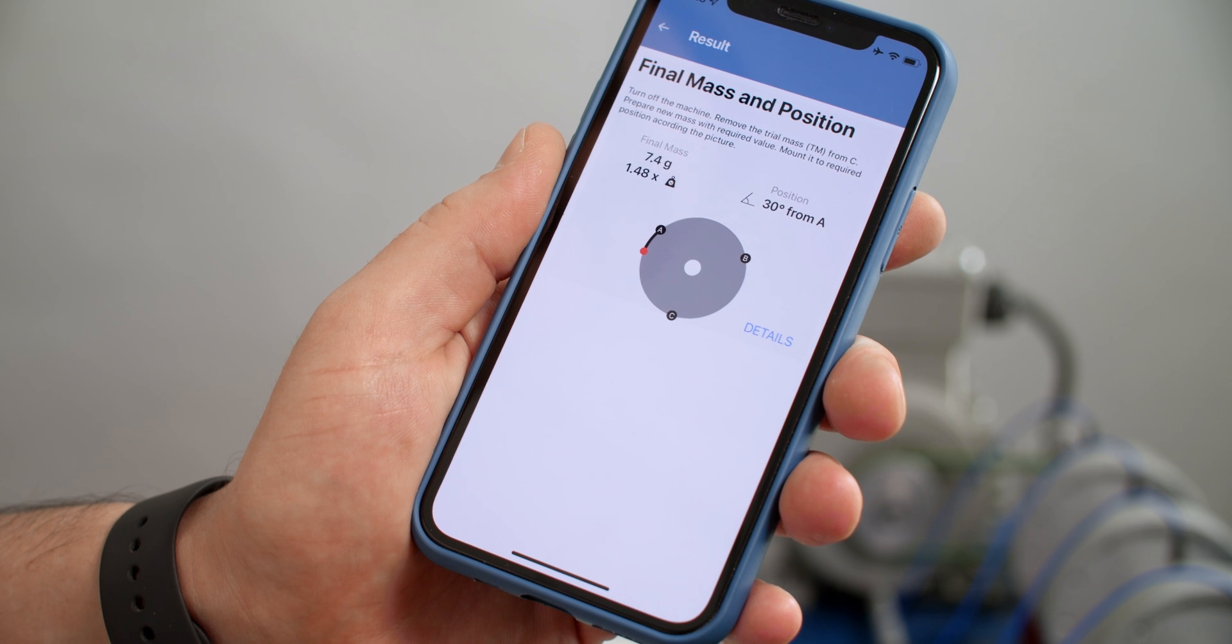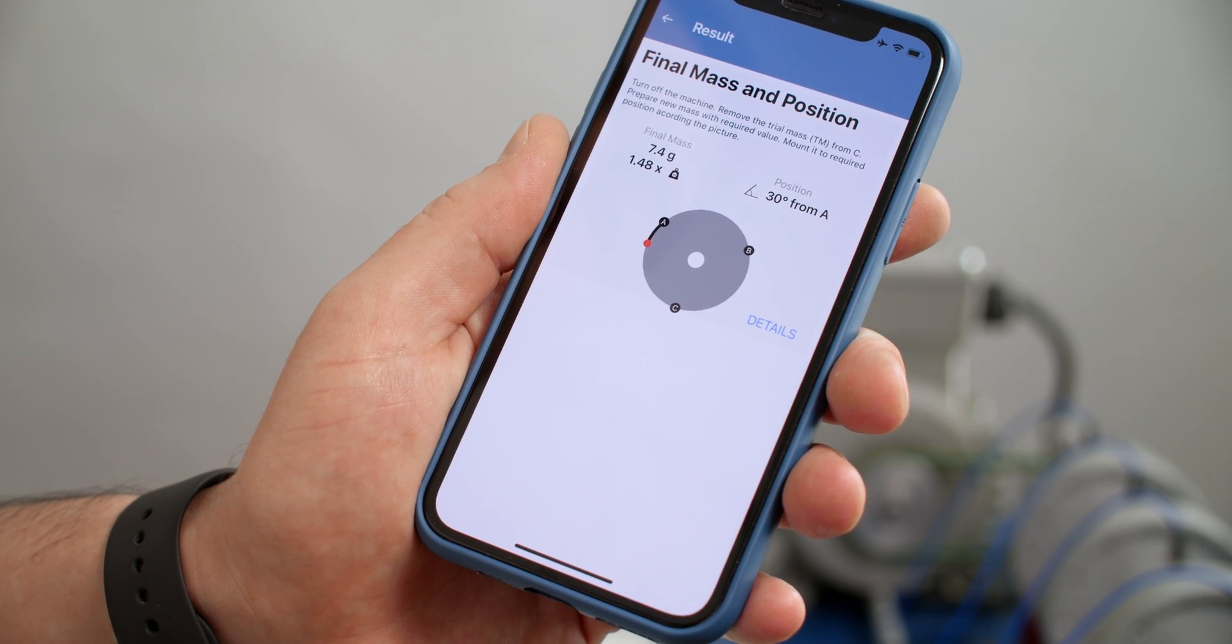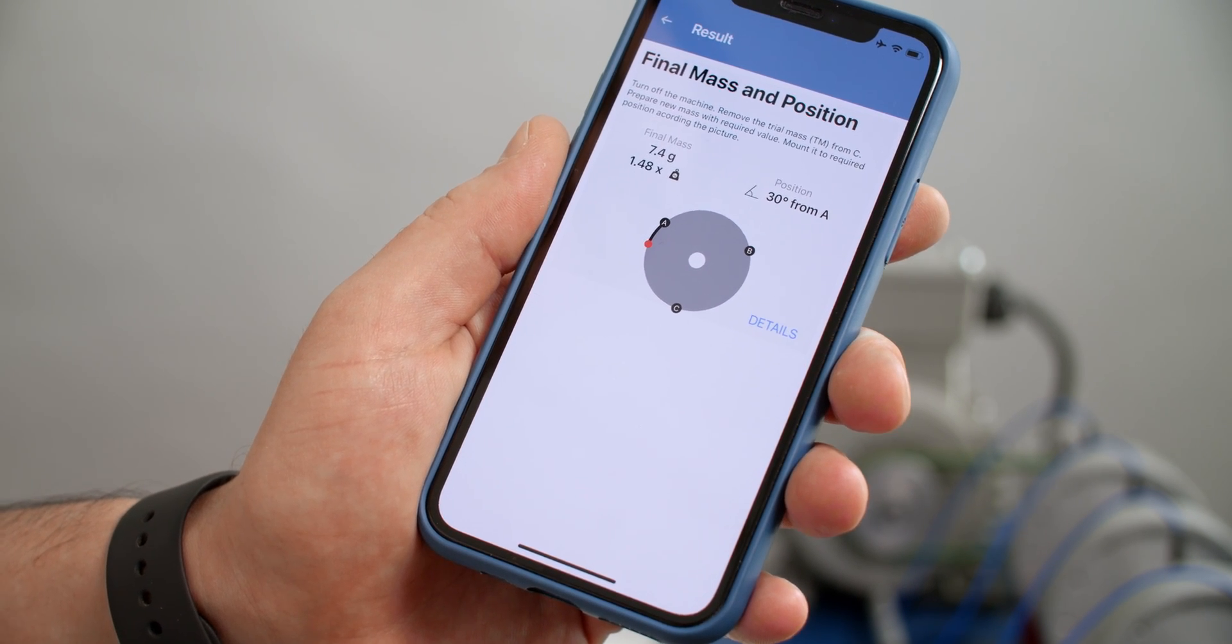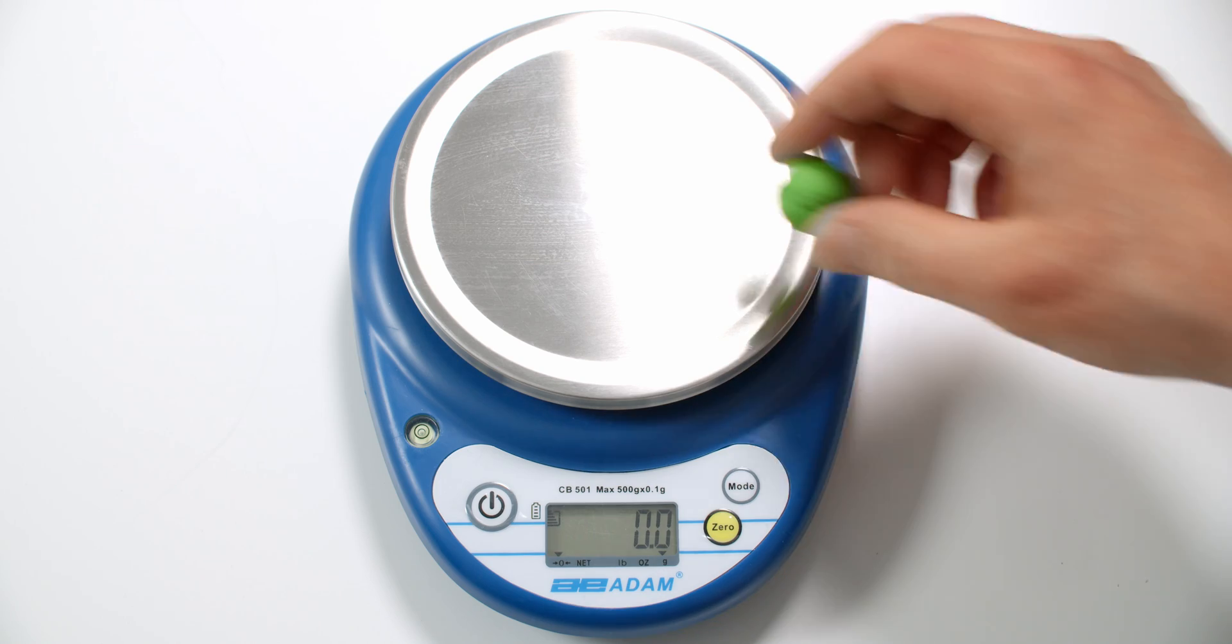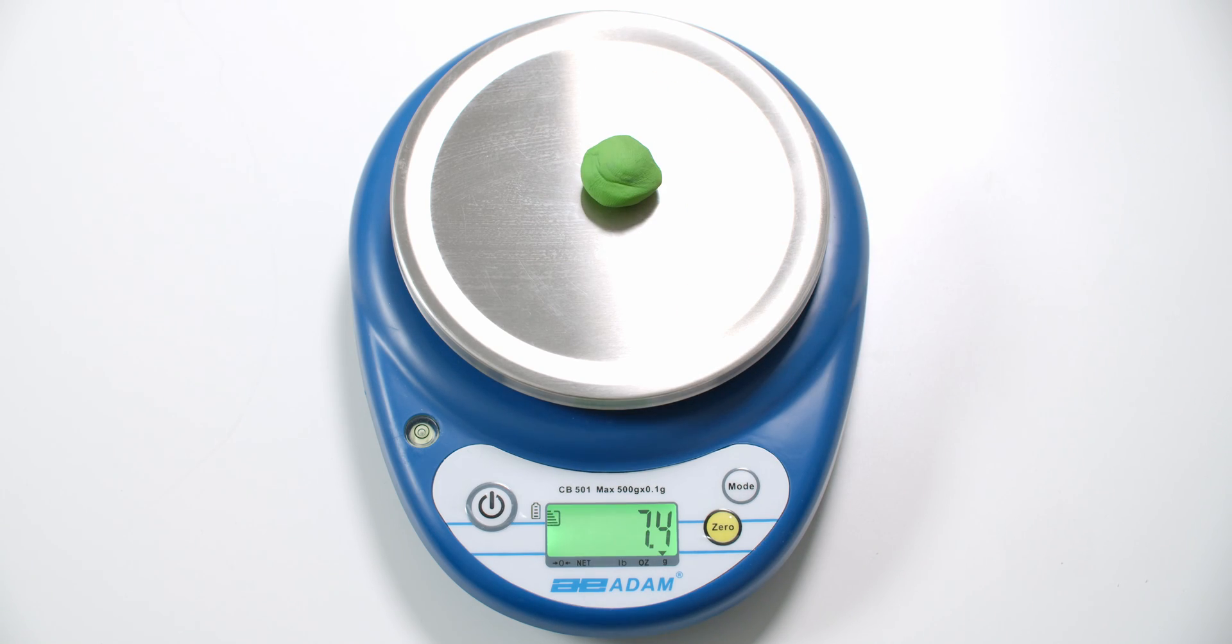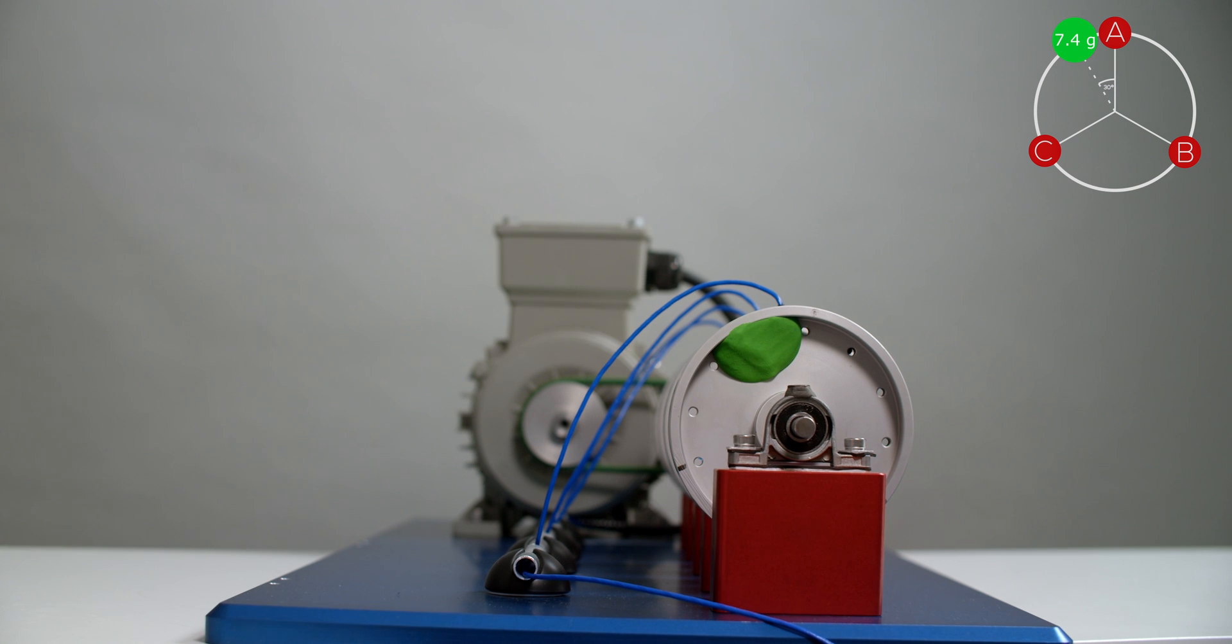The app will calculate and advise how much the final balancing mass should weight and where should I place it. In this case I should add 7.4 grams into 30 degrees from A position.